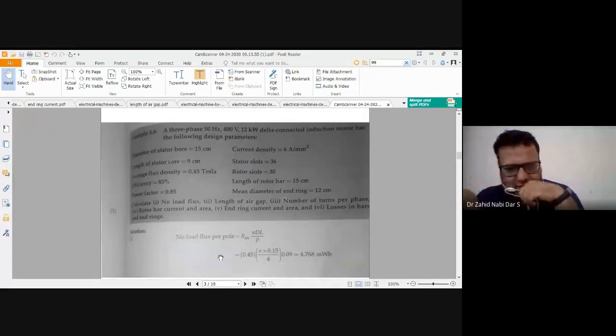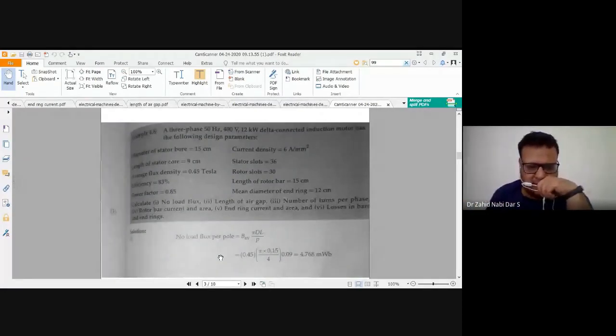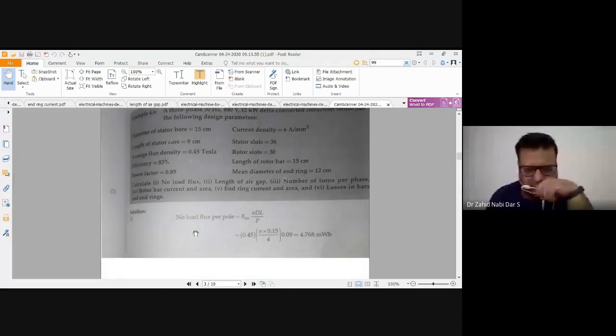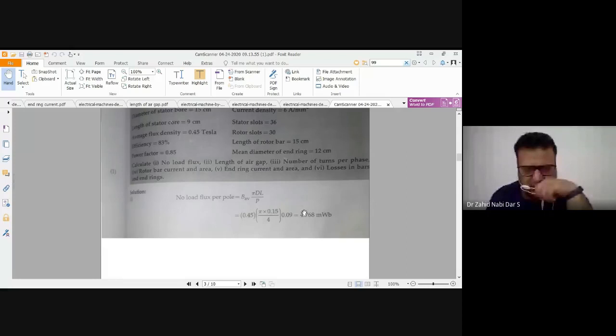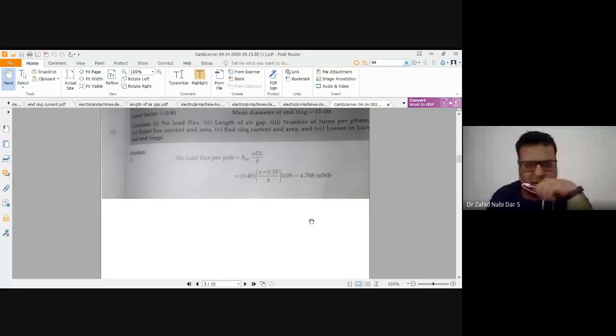So I was with this problem: a three-phase 50 hertz 400 volt 12 kilowatt delta connected induction motor has the following design parameters. So these design parameters are there. First of all, I calculated my flux. Once I got my flux by substituting in this formula, it is 4.768 milliweber. Number of poles you take down as 4 and your average flux you take down as 0.45.